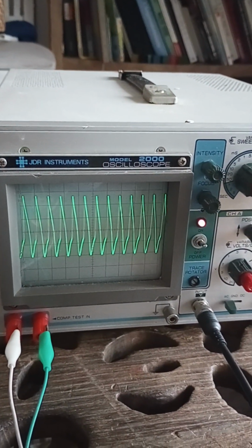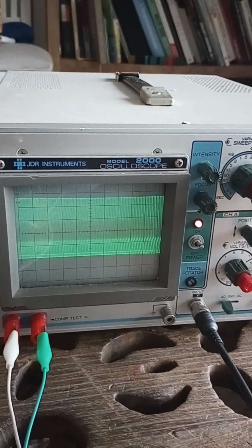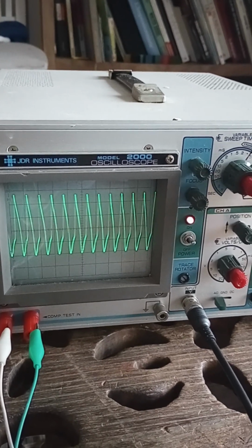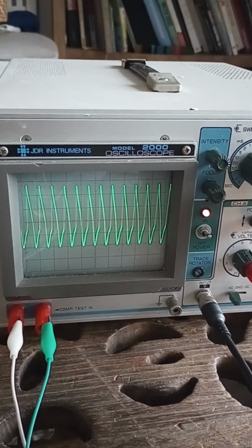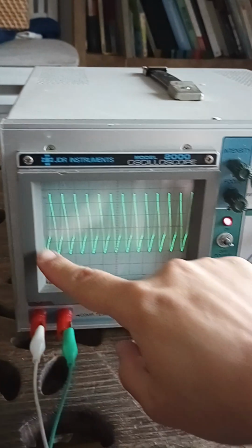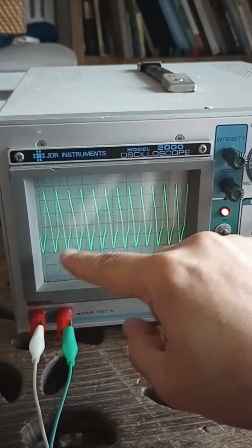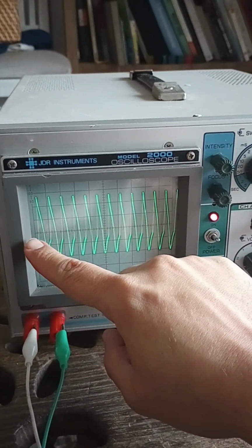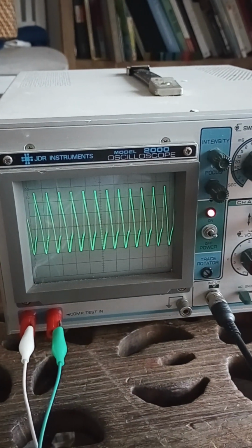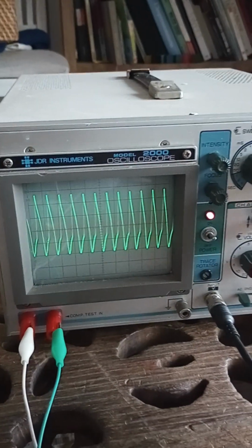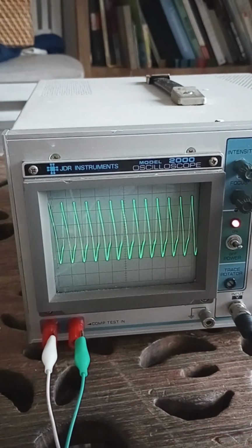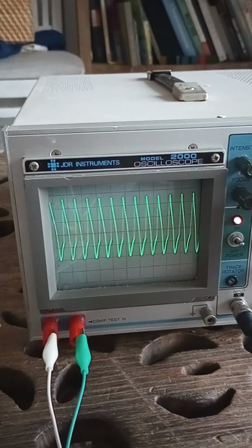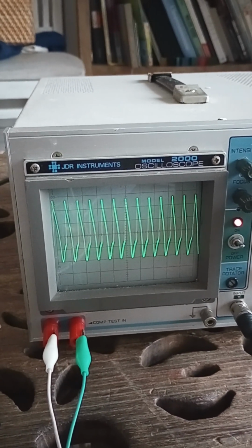I can change the trigger here, and so inside the window I trigger at different values, and when I'm outside of the window, I just lose the trigger. Okay, so this is for negative slope, so it's triggering at this value for negative slope. If I change the value, I'm triggering higher with a negative slope. If I change the slope, I'm going to trigger at the same value, but for signals that go up. Let's do that. And right there, you can see that it's starting at signals that go up.